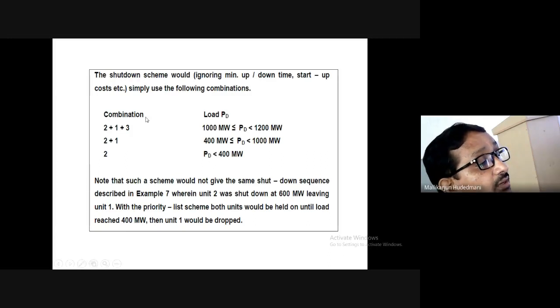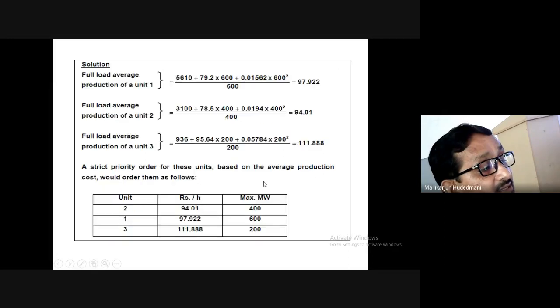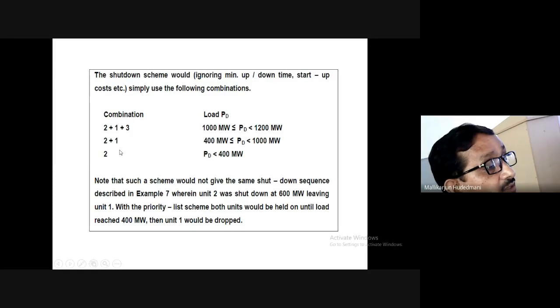This is how the shutdown scheme or particular priority listing method is given, ignoring those things. Combination, demand. So priority is 2. When the priority is 2, up to 400 it can serve. The 2 and 1 combination covers 400 to less than 1000, because its capacity is 600; when I add, it becomes 1000. Up to 1000, 2 and 1. Above 1000, up to 1200, the 2, 1, 3 combination.